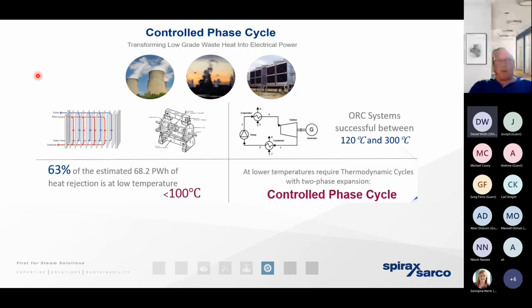Well, many of us are already familiar with a traditional organic Rankine system, and that can traditionally only take the waste heat energy out of an effluent stream at temperatures in excess of 120 degrees. Well, we've got a product that we call the CPC, or the controlled phase cycle. And that's able to take the energy out of waste effluent at much, much lower temperatures, typically as low as 70 degrees. But obviously, the higher the temperature, the more waste heat energy is going to be available for reuse.